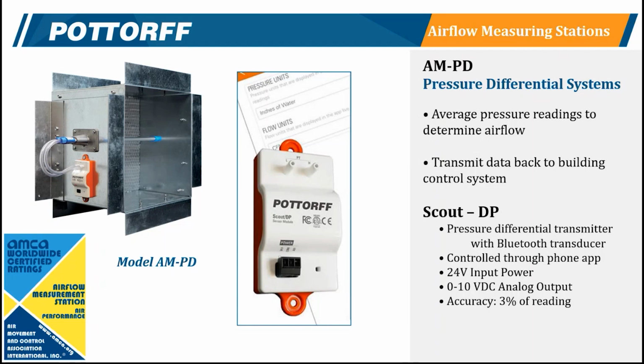Now this is a pressure differential system. So when you're talking about airflow measurement stations, which are newer to Pottorff, there are two main types of technology available. There's thermal dispersion, which you'll see when competing against, say, Ebtron or other players in the market that use a thermistor and a temperature sensor to calculate airflow. Pressure differential systems work a little differently, as they use a high pressure and a static pressure comparison to set that airflow.